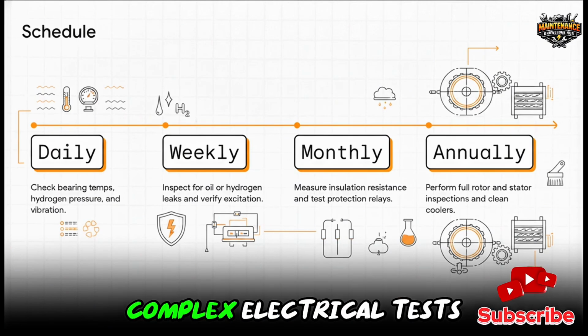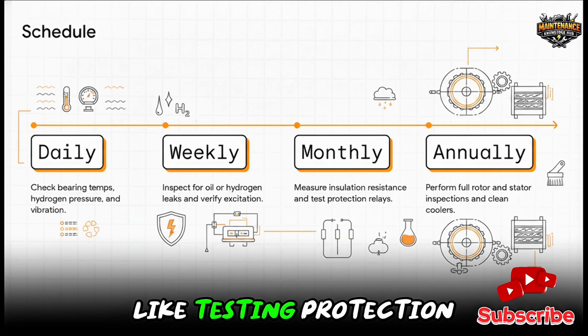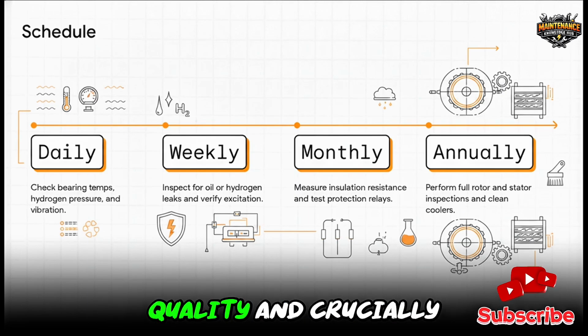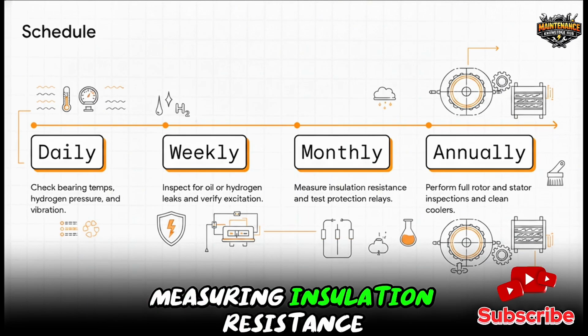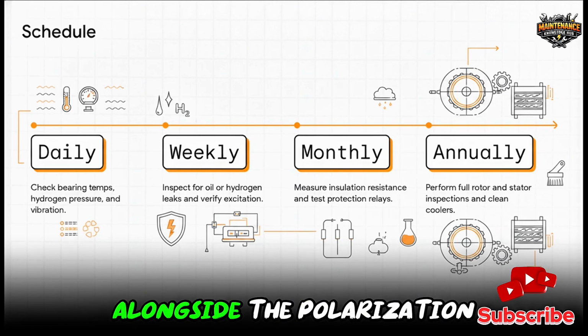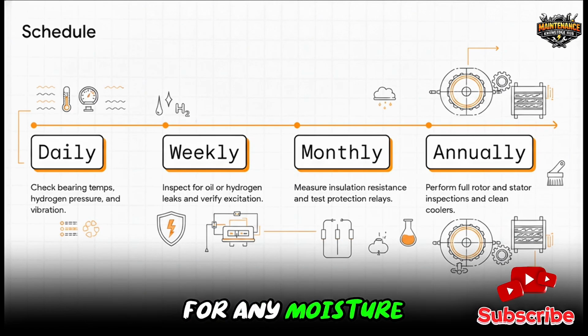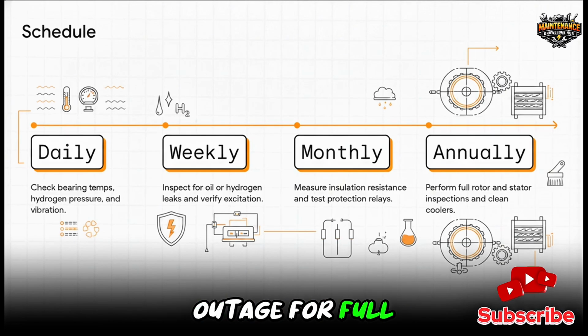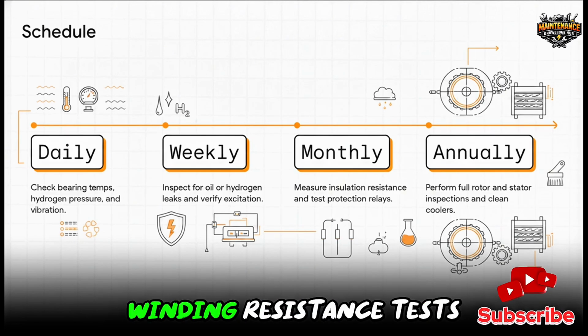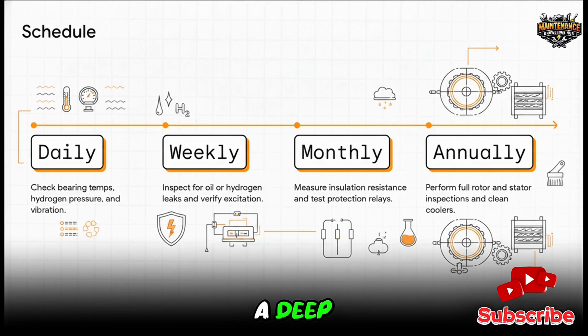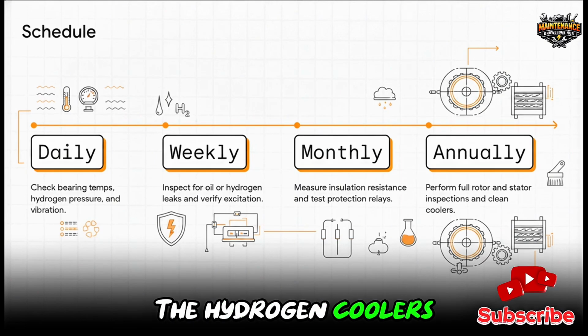Monthly, we get into the more complex electrical tests, like testing protection relays, checking bearing oil quality, and crucially, measuring insulation resistance, or IR, alongside the polarization index to check for any moisture creeping in. Annually, that's when the plant schedules a major outage for full rotor and stator overhauls, winding resistance tests, alignment checks, and a deep cleaning of the hydrogen coolers.